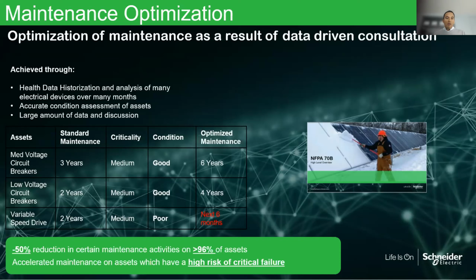And having that discussion with the customer, we're able to advise. We can say, your medium voltage breakers have been running at about 30% load. The environmental conditions—humidity, temperature—are controlled, salinity is not a factor, and you've opened and closed the breaker in the last year, so the mechanism is fine.